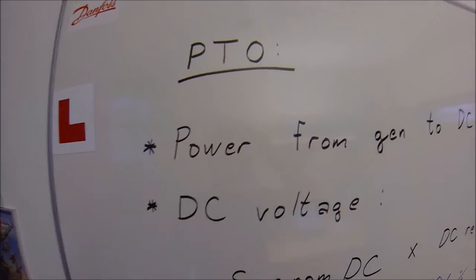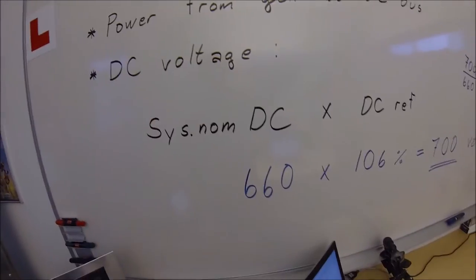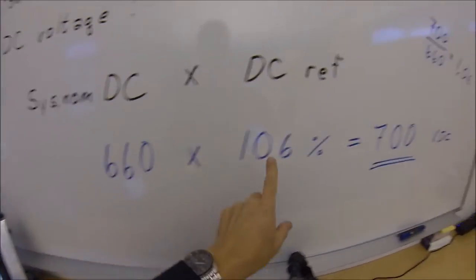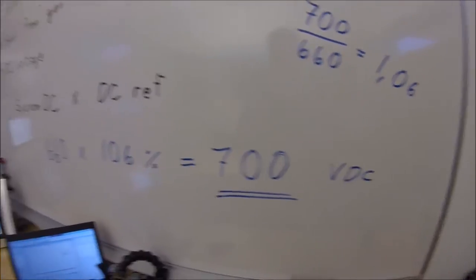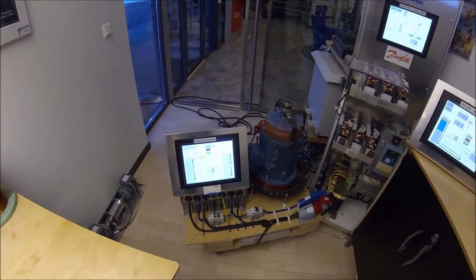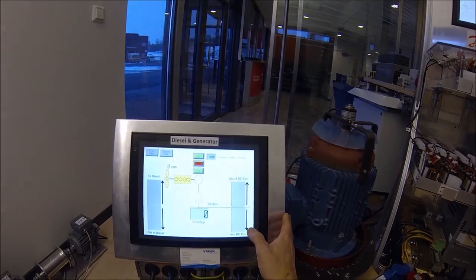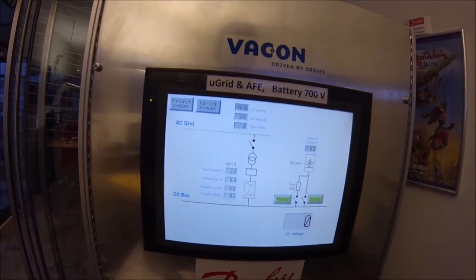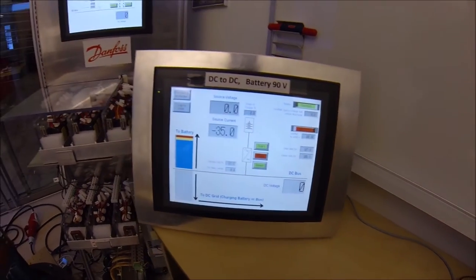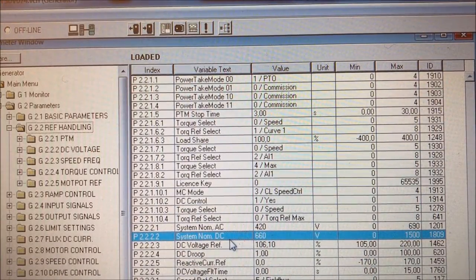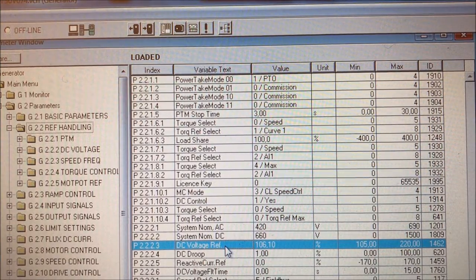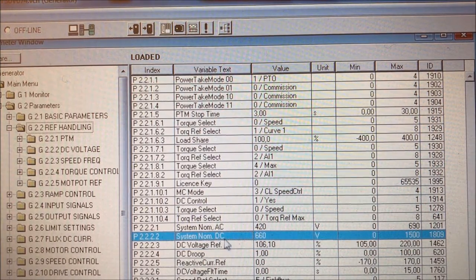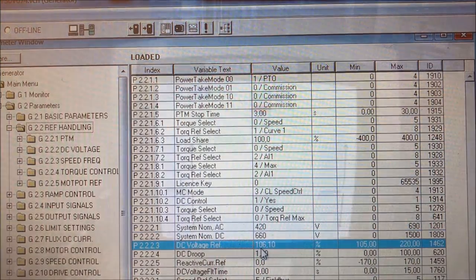When running in power takeout mode, the power goes from the generator to the DC bus, and the DC voltage will be the nominal DC voltage multiplied by a DC reference — in this case 700 volts. The parameter for the system nominal DC multiplied by the DC voltage reference will set this voltage. In my case I have a system nominal DC of 660 and a voltage reference of 106.